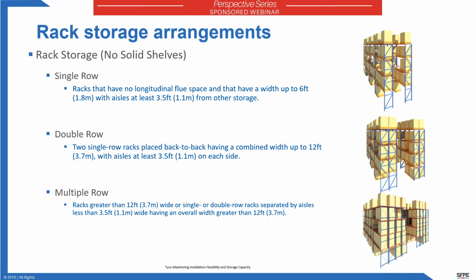All right, so I'm going to get into a little bit about rack storage arrangements. So racks, you see some slides there. There are essentially three different types of racks in general. Single row rack is just one row of an open rack. They do not typically have solid shelves, and you store pallets on them. So with single row rack, you have one rack that's essentially the width of a pallet, and they're separated by aisles. A double row rack, as you see in the diagram, shows two single row racks that are back to back, and then they're separated by an aisle. And then if you have more than a double, then you get into multiple row racks. So each one offers challenges with regards to fire protection schemes.